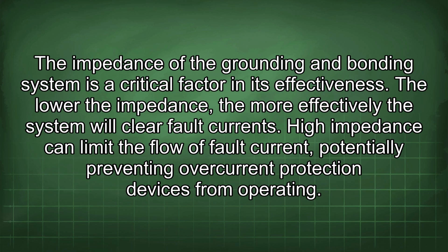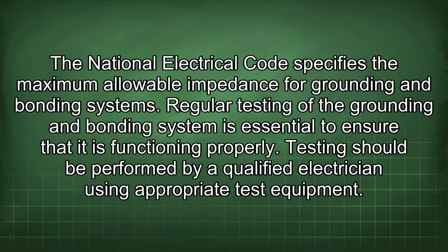The impedance of the grounding and bonding system is a critical factor in its effectiveness. The lower the impedance, the more effectively the system will clear fault currents. High impedance can limit the flow of fault current, potentially preventing overcurrent protection devices from operating. The National Electrical Code specifies the maximum allowable impedance for grounding and bonding systems.